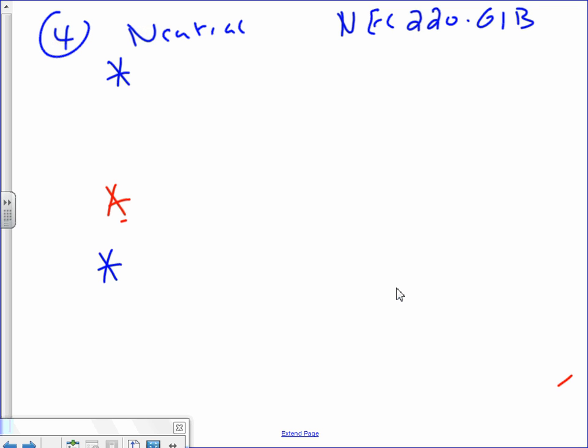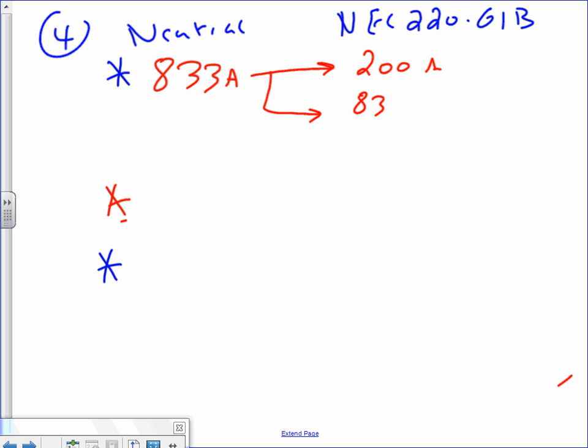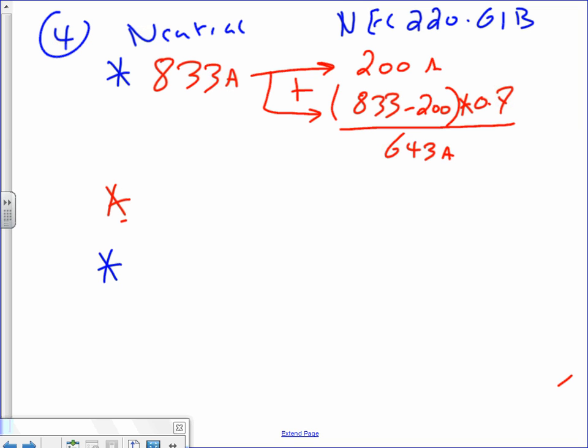So here's what we're going to do. We take the 833 amps, apply the demand for it. The first 200 amps shall not be touched. Then you come over here. So 833 minus 200, multiply by 0.7, and add your answer, and you should come up with 643 amps. Now what the heck is that plus?